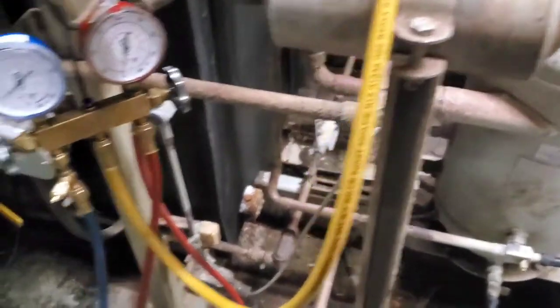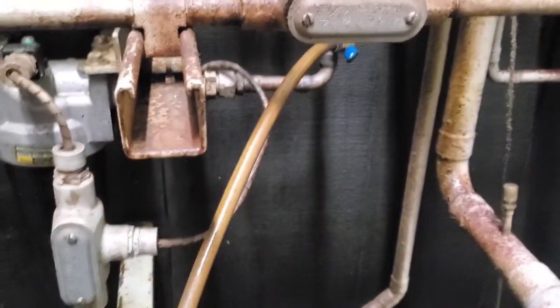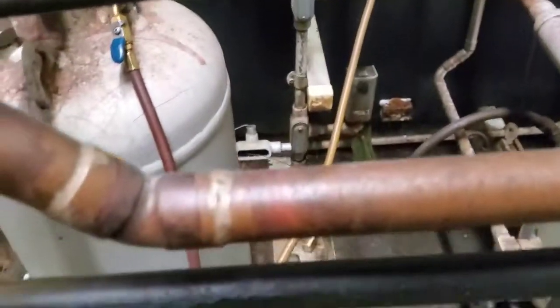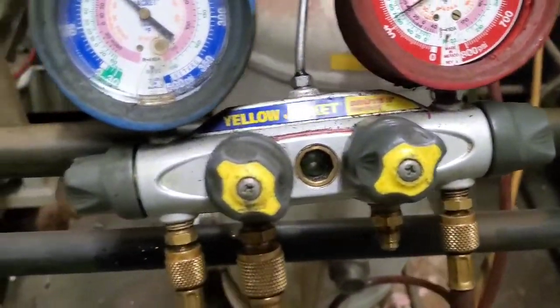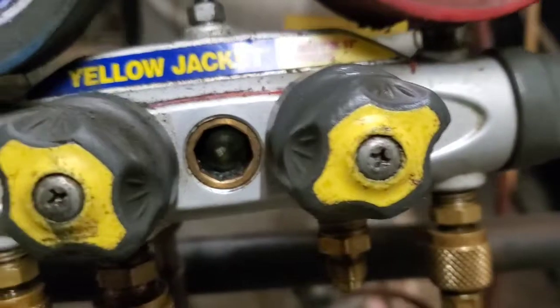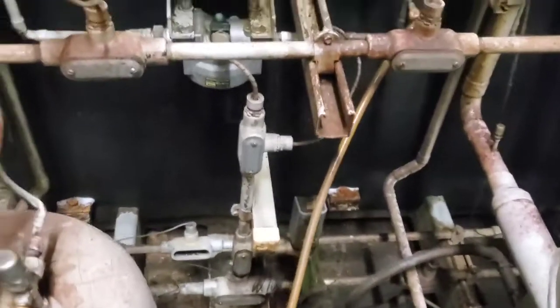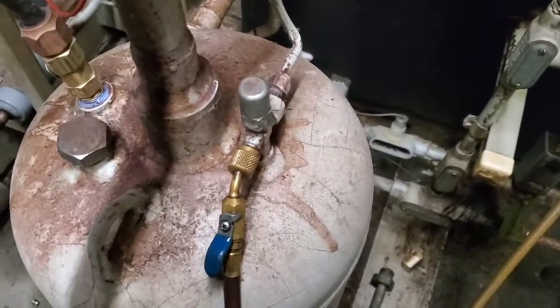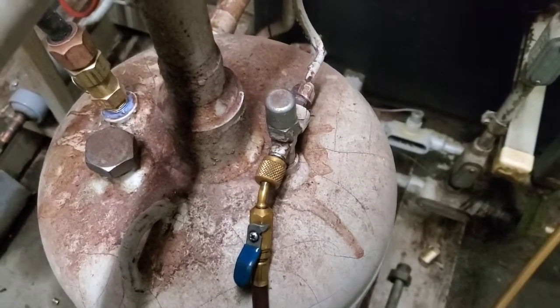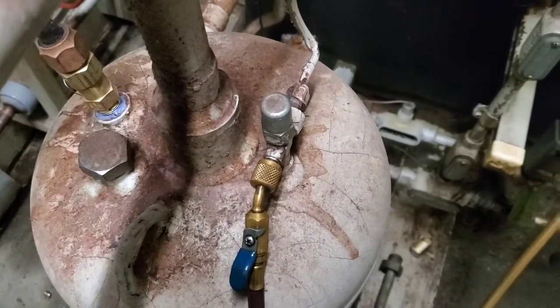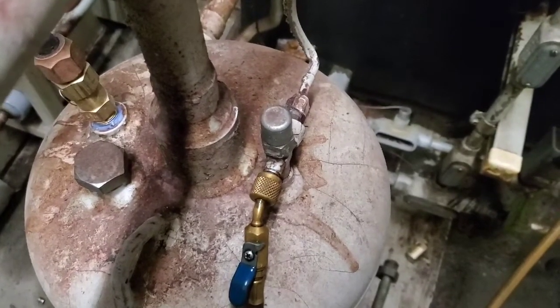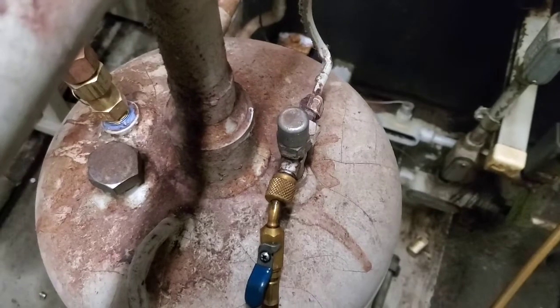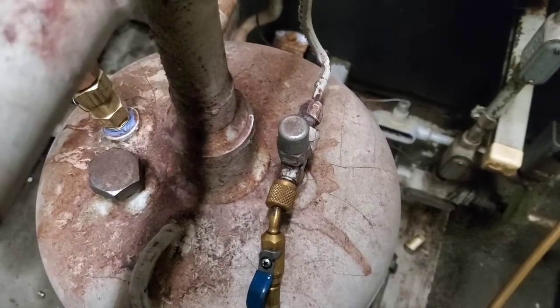I've got some junky gauges that I use for this, but the hoses are clean. We come out of this yellow hose and we go into the top of that oil circuit. The bottom of this oil circuit, we're going to go through another set of gauges, and these gauges have a sight glass. We're going to start pushing oil, and you're going to see oil flow through that sight glass, coming out of the suction hose, which is normally your suction hose, and back into the top of this oil separator. So we're not recovering any refrigerant, we're not pulling any oil out, we're simply displacing the oil with refrigerant, and then we can pull the refrigerant and put it back in the same system. So no recovery tanks needed.